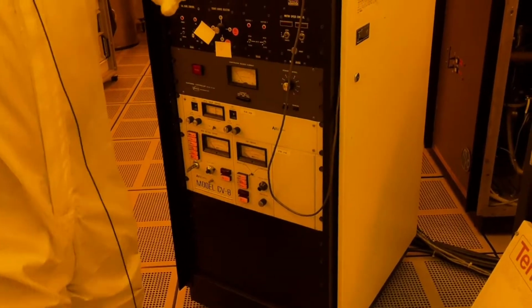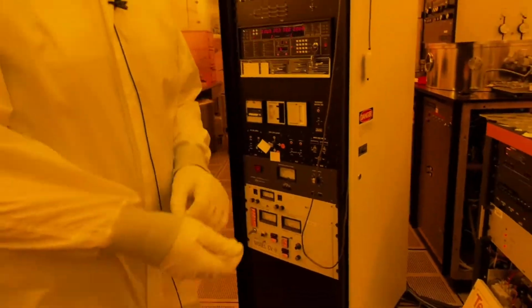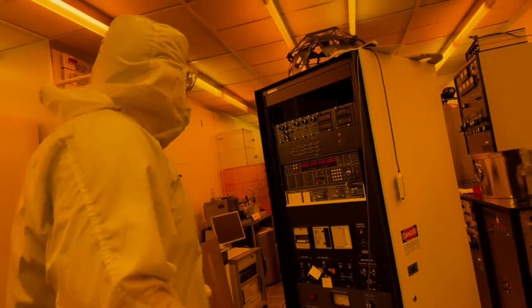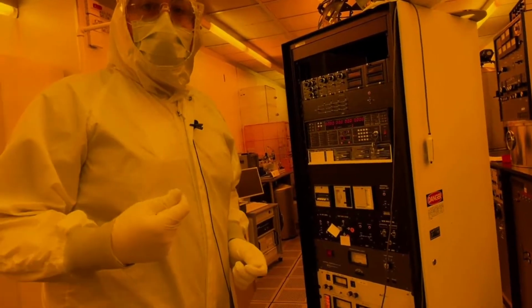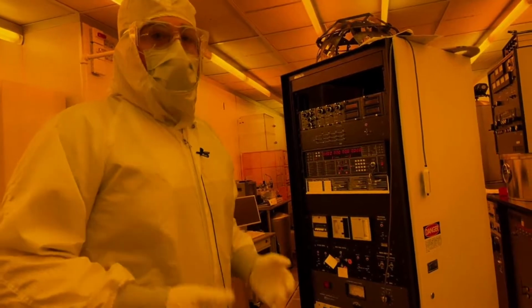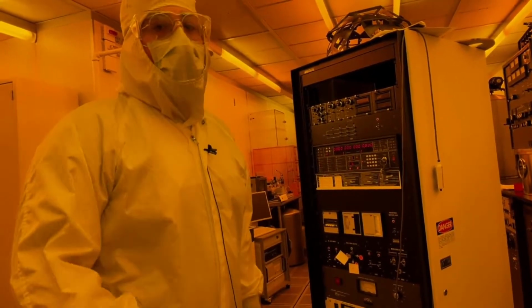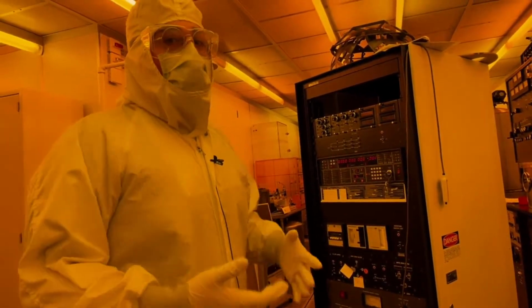Basically, the problem here is that the relays in this high voltage source are pretty old. So you have a step start circuit. If that gets tripped and it's not working properly, it may take a couple of times for you to turn it off and on for the high voltage to pop up.